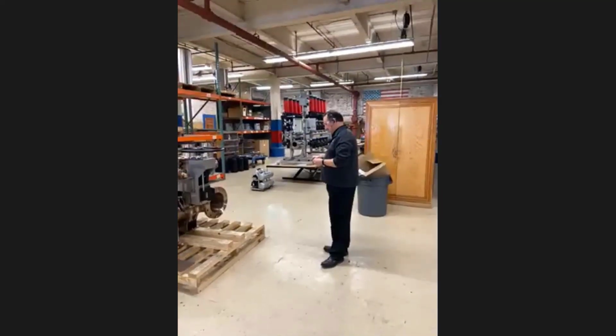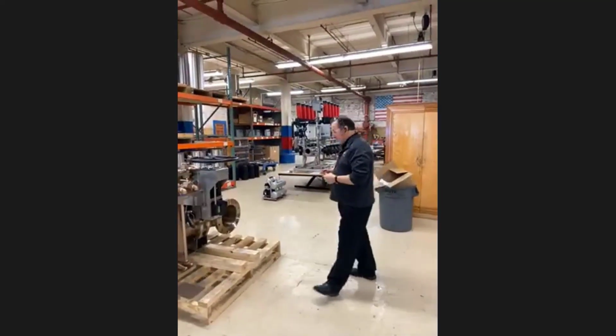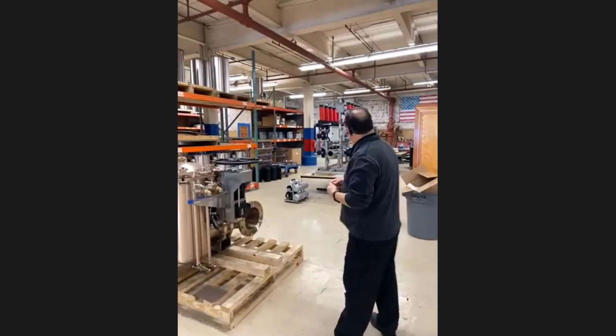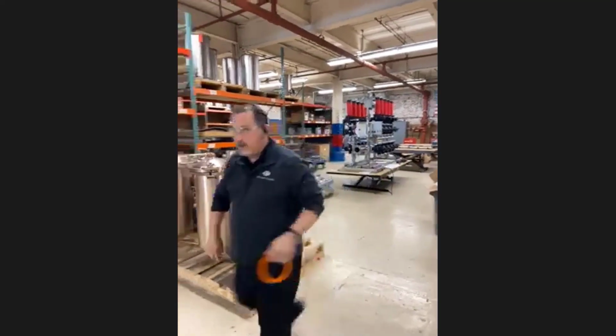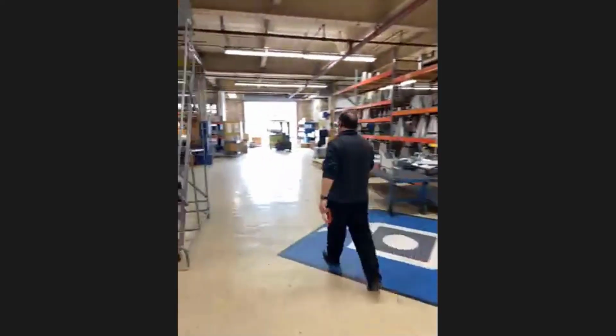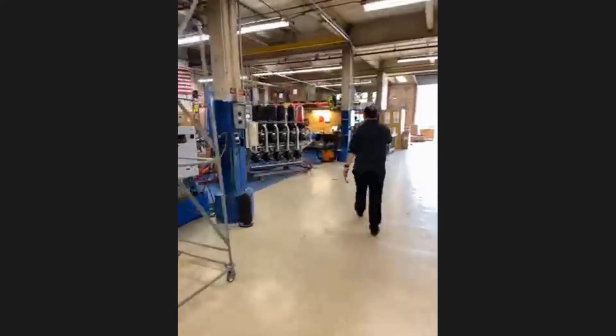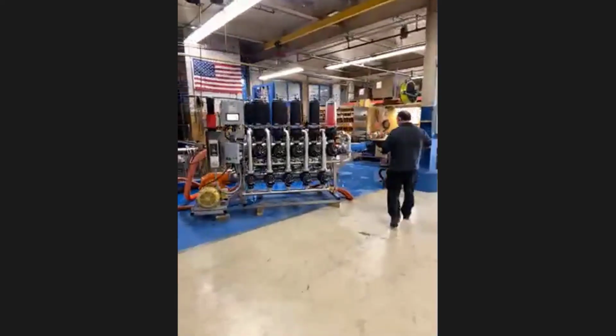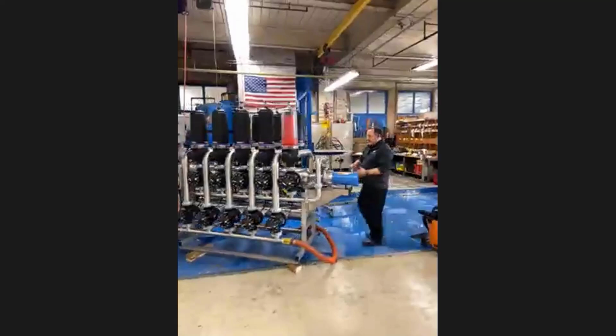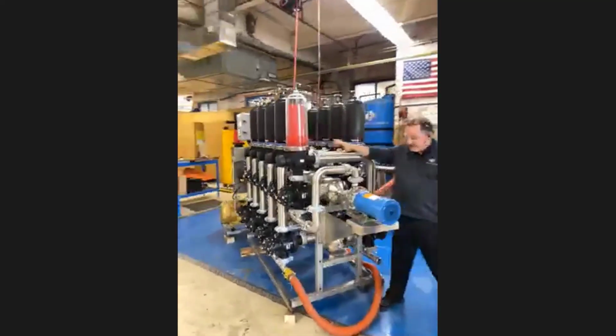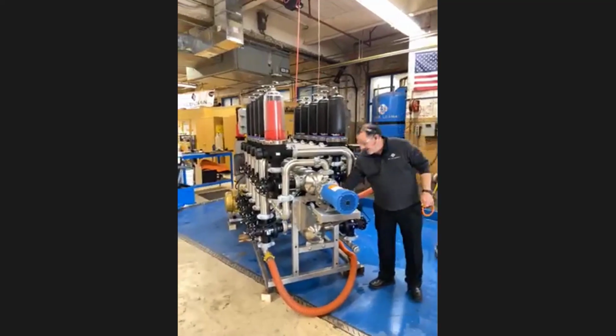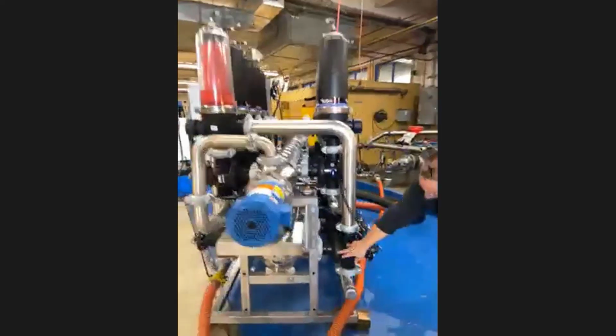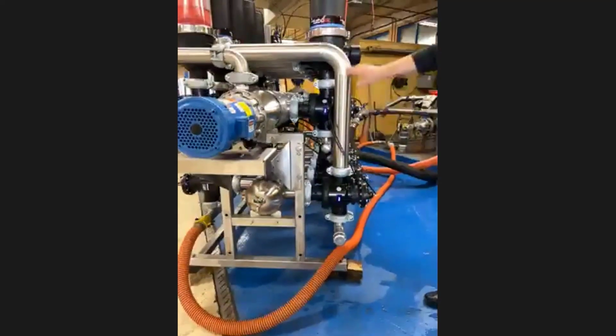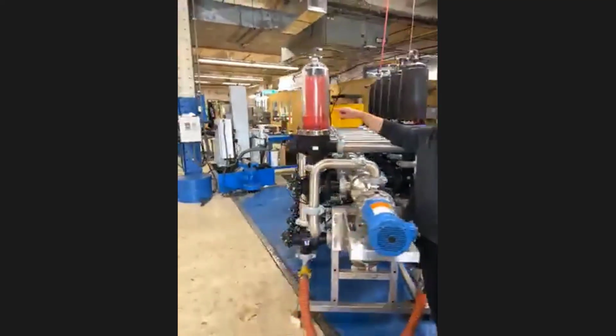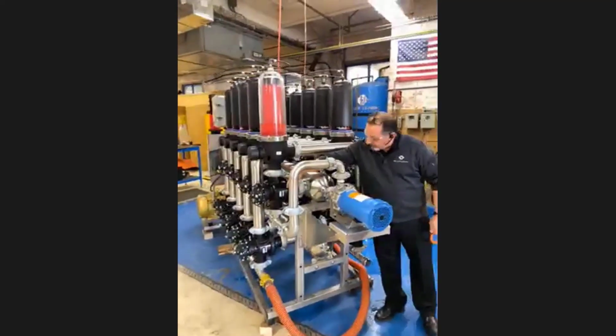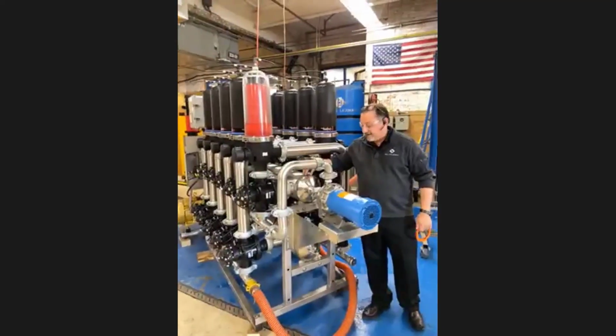on the backflush flow path? I don't know if you want the unit in front of you or the one behind you that shows a good flow path. Let's go back to the other one over here. The backflush flow path, good question. Basically we're going to go back to the pod that was being backflushed. This pod right here is the one you could see being backflushed. Coming from the dirty water side, this connection right here, it comes into the valve and the valve is open like an L like this, where the dirty water comes up into the housing, spins, filters through the disc, comes out, L back into the clean water side, back into this manifold.